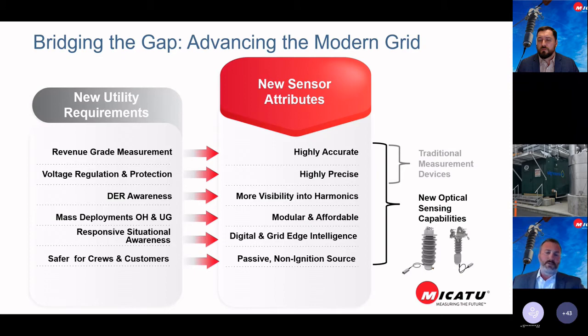Optical sensing technology goes a step above and beyond what traditional technologies have been able to do. Legacy technologies like PTs and CTs provide voltage and current information, some phase angle, and some level of harmonic information. Optical sensors can do that and then some — gathering very granular data out to the 250th harmonic level on voltage and the 11th on current, plus detailed power factor information, non-shifted phase angle, full temperature range data, AC/DC basic information, and total harmonic distortion.